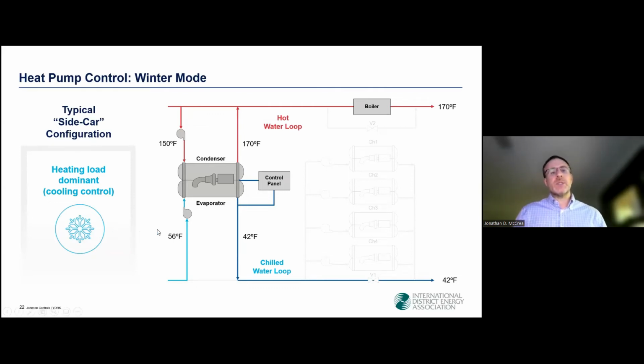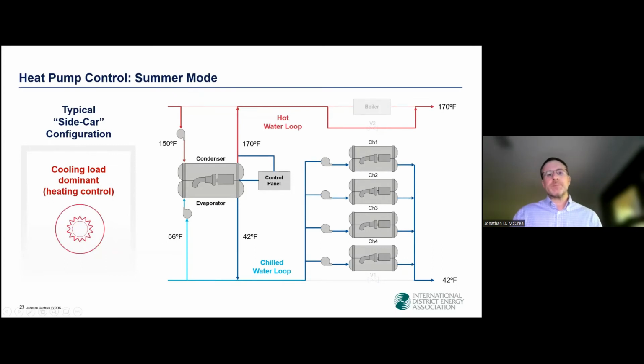So if we look at that same system in summertime operation, what we have here is a lot of chilled water load and a relatively small amount of heating load. So our heat pump, again, having been carefully sized to comfortably unload and continue to run, handling the summertime minimum hot water load, it's receiving all of the system's 150-degree return hot water flow through its condenser, and then its onboard controls are delivering the 170-degree supply hot water temperature that's required by the system.